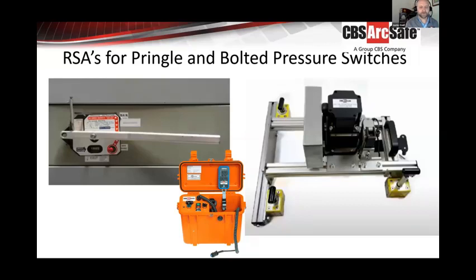For a couple things on the racking, on the universal racking system, there are two protection elements. One is we monitor amperage, and we also have a physical clutch setting on the end of it. So what we do is try to set that so it doesn't over torque the breaker. If we know a breaker has a shearing pin of 25 foot-pounds, we don't set that clutch any higher than 20 foot-pounds, so it doesn't exceed the shearing pin.